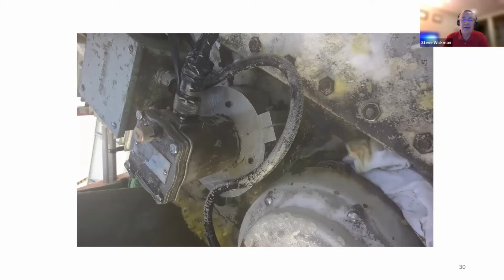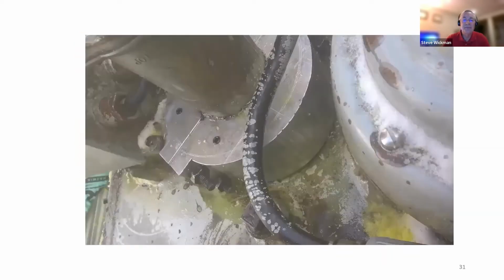One thing I like to point out in this picture too is notice the snow that's on some of the other panels up on top of this transformer. So it was a bit chillier when this repair was actually done. And it kind of gives you the clue that this work can be done both warm weather, summertime, cold weather, wintertime. Biggest limiting factor really with the cold is just the extreme for the poor technicians doing the work. But weather does not matter, summer, winter, hot or cold, the same repair technique is applied. Just another view, another angle of this clamp.